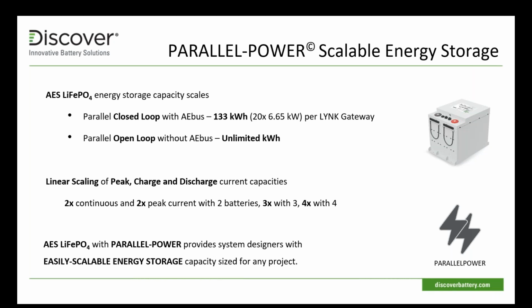Additionally, our batteries parallel very well. Scaling is very simple. If you've installed a lead acid battery, you can pretty much install our battery. The installation of cables and sizing of cables is exactly the same as a lead acid system. There's really nothing new to learn there. There's no fancy system that needs to be employed using a bus bar system or a series-parallel connection of batteries. No problem with that.